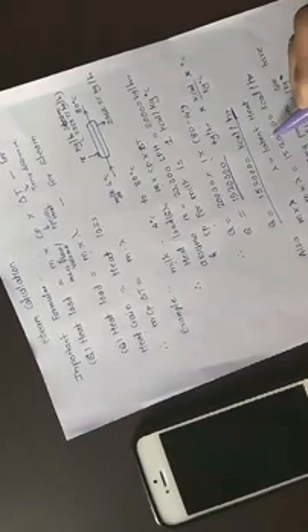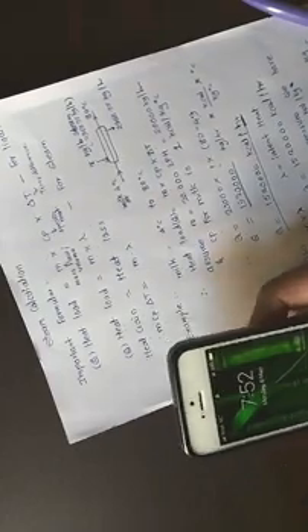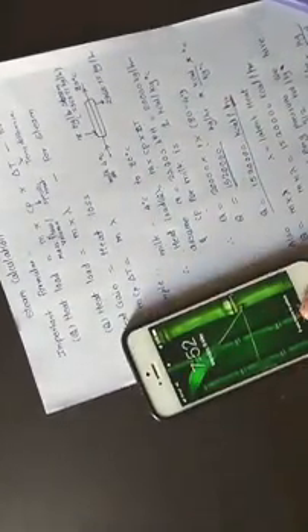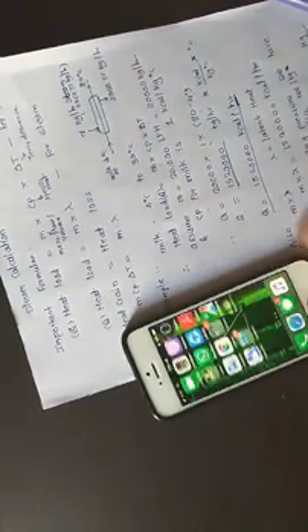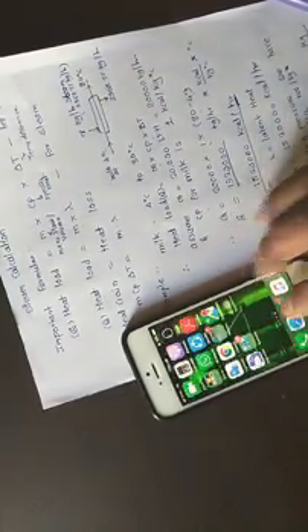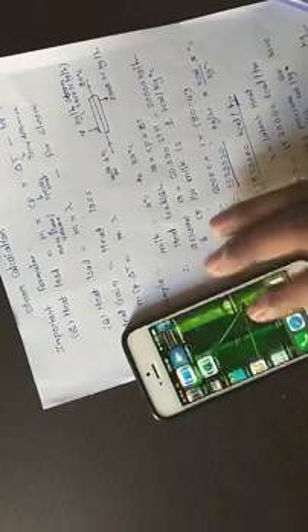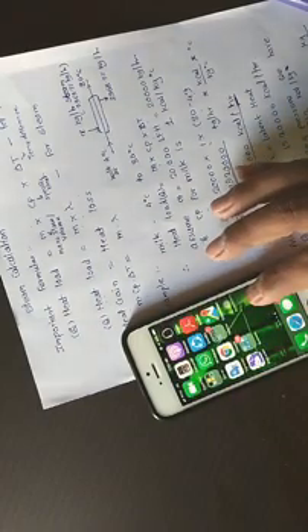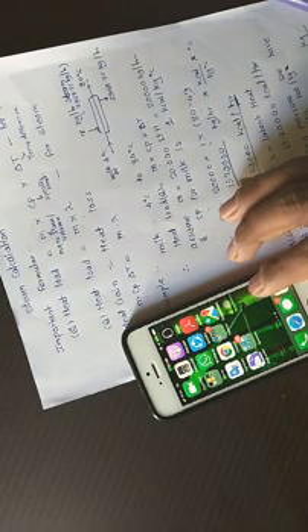Now we have to equate it with the steam load. So Q from the steam side is equal to M lambda. Lambda is the latent heat. From the steam table at 3.5 bar pressure, we have a temperature of 143 degree Celsius, and hence lambda is 512 kilocalories per kg. If you are not comfortable with the steam table, then you can use a steam tool to calculate the latent heat value. You can download it from the Play Store.